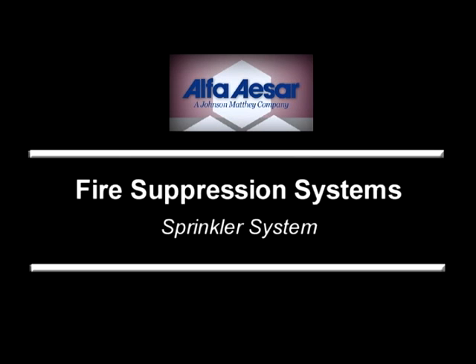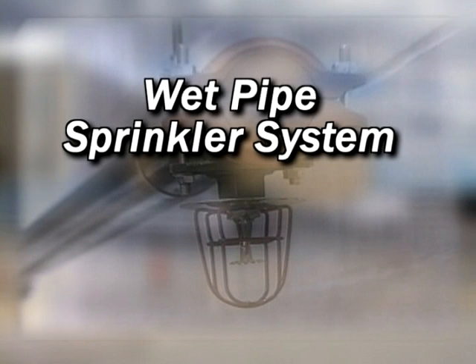Sprinkler system. The basis of design for the wet pipe sprinkler system is NFPA 13, with storage areas of the facility considered as ordinary hazard Group 2 occupancy and office areas considered as light hazard. This includes the corrosives, flammable solids, oxidizers, common corridor, and office administrative areas.